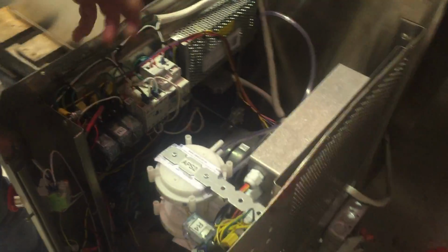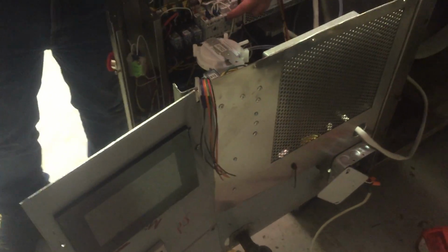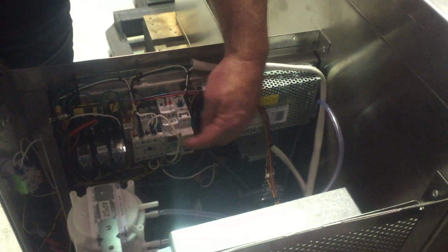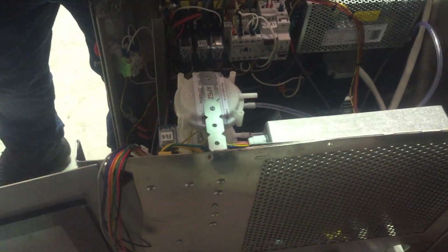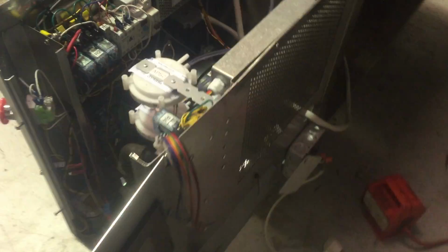So basically when you turn the fan on or the blower on, that counts down 30 seconds as a sweep timer, if you like. And then it sends a signal to the ignition module, which starts the ignition process.